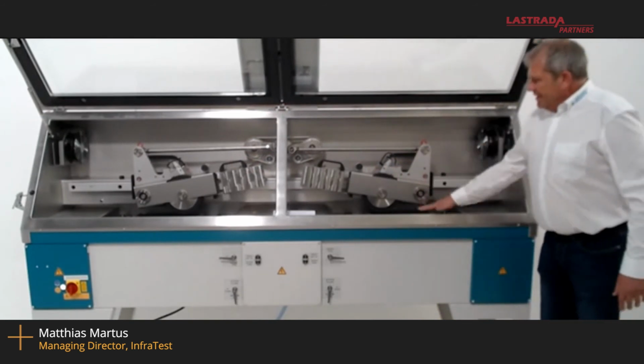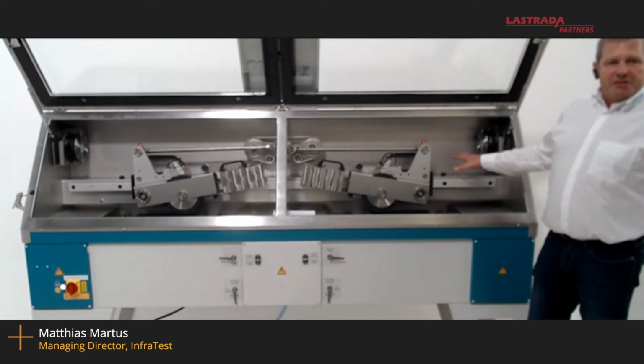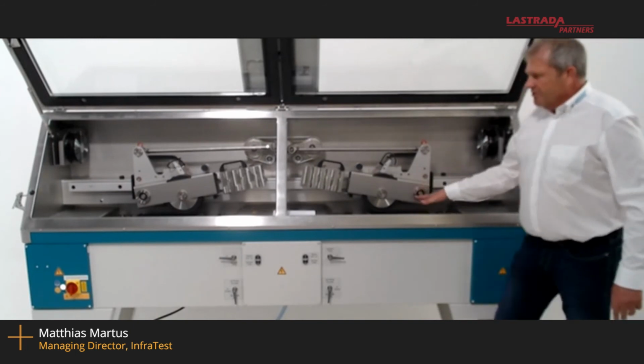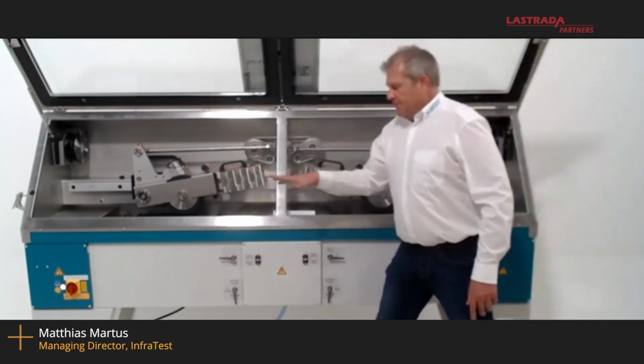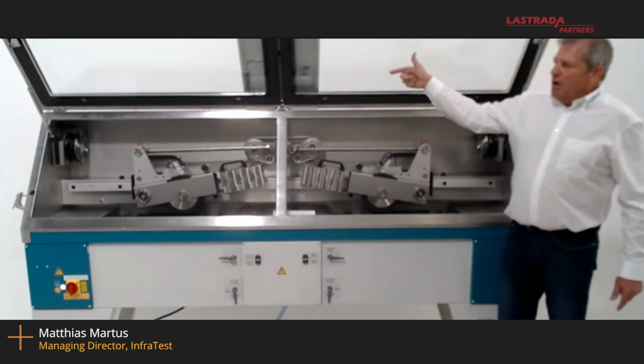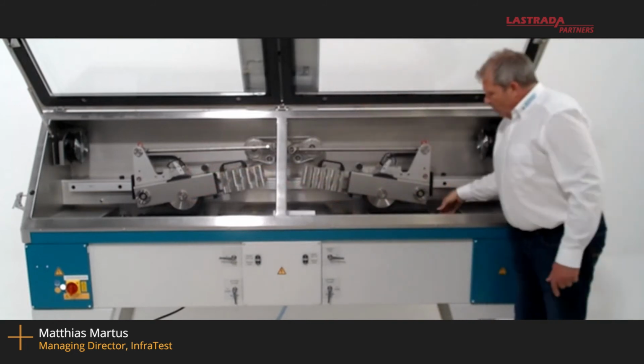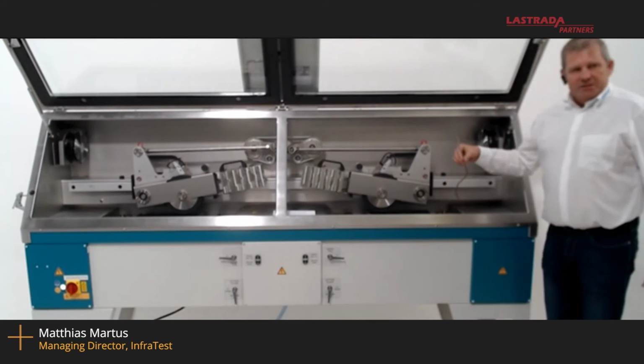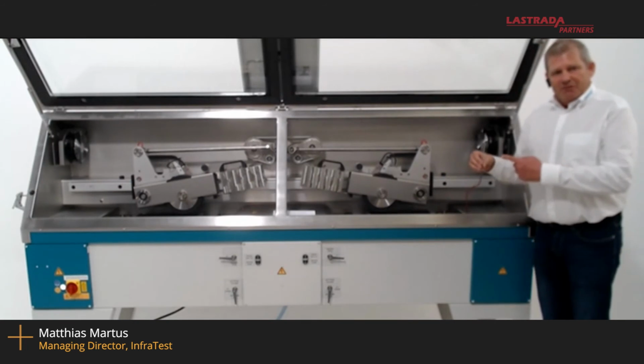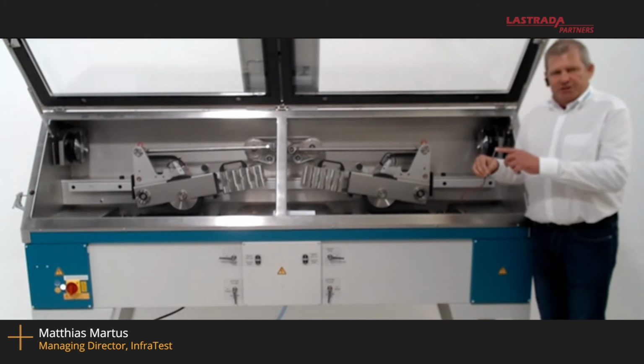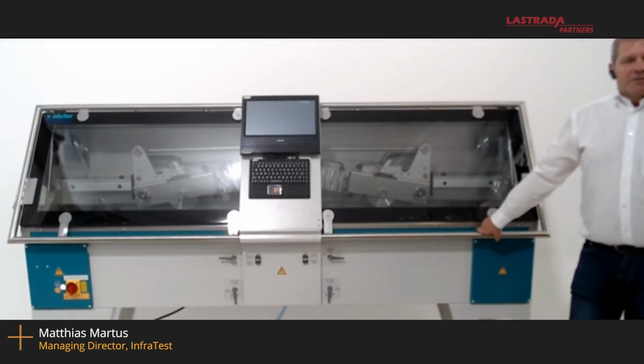So on every side we have 3 independent heating systems, 3 on this side and 3 on this side. For measurement, there is one central measurement behind the machine, and one measurement is fixed on the sample itself, so we can measure the exact surface temperature with this PT100 system. We can measure as much as we like. At this moment, we make 15 measurements per side over the central 100 millimeters.